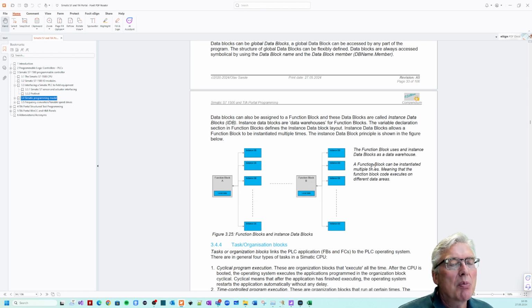So we have a lot of function blocks. A modern PLC program is about programming function blocks and interconnecting them to do whatever your control should do, and getting rid of FBD and ladder. And if you want to use ladder, God forbid, for combinatory logic, use ladder and not FBD, because it's easier to follow the power flow than decoding complex AND, OR, NOT and so on down here. But of course, avoid it altogether.